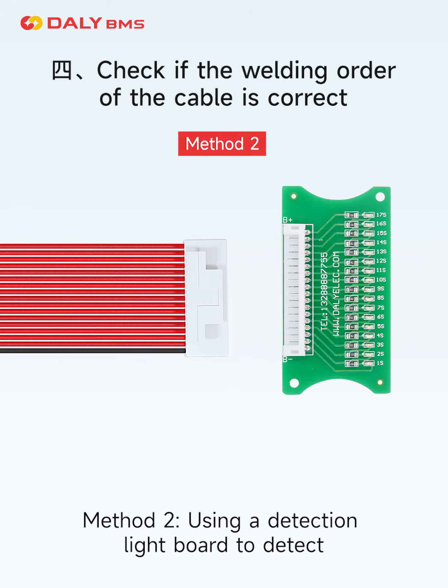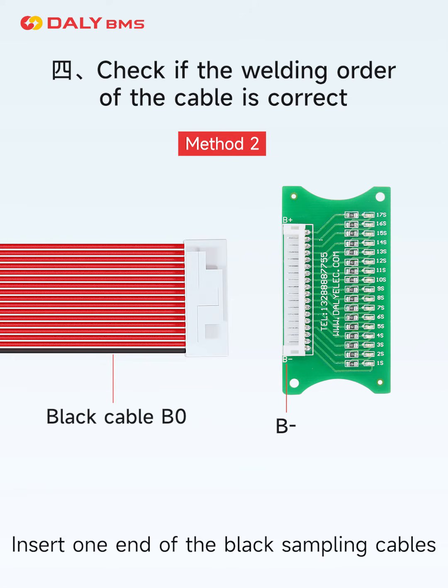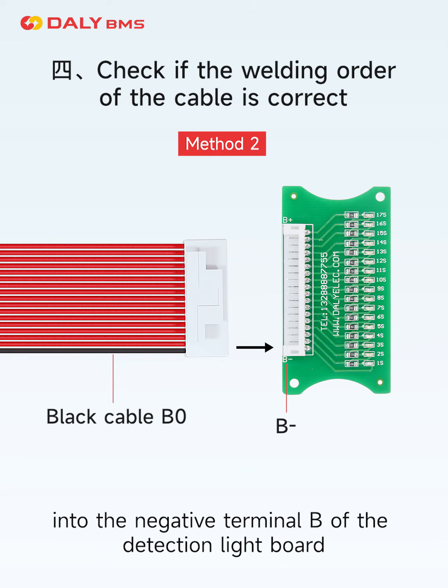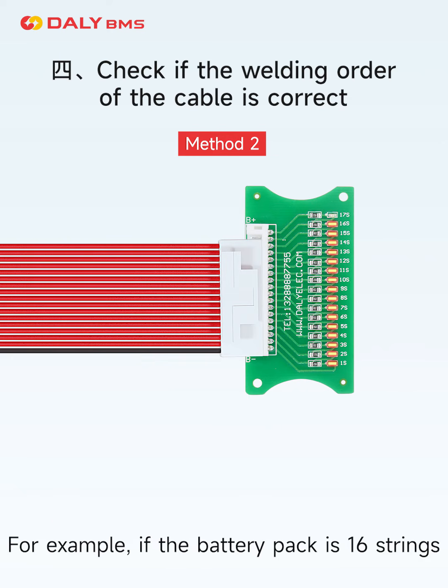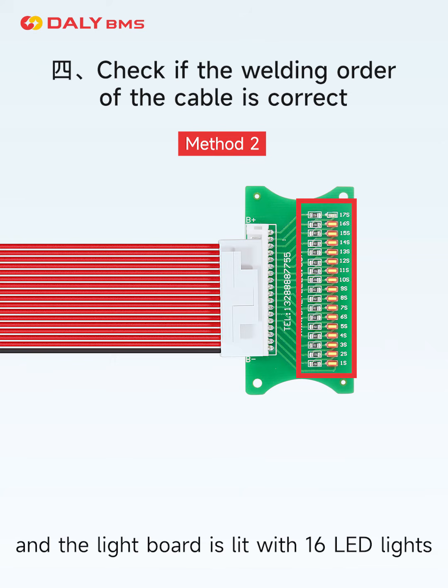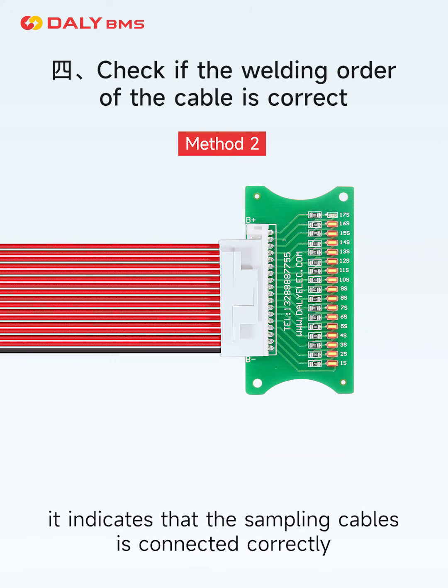Method 2: use a detection light board. Insert one end of the black sampling cable into the negative terminal B of the detection light board. For example, if the battery pack has 16 strings and the light board lights up with 16 LED lights, it indicates the sampling cables are connected correctly.